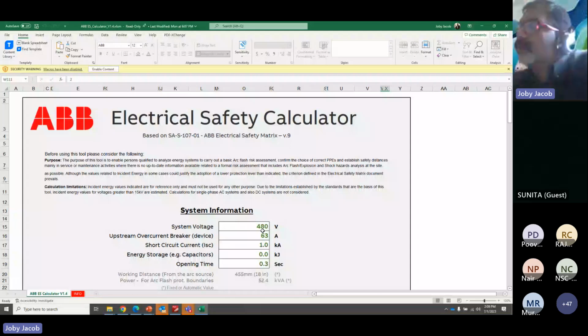And the other important thing is your relay settings, how you set, whether it is instantaneously set or a time delay or something like that. So this is the common mistake also people do. In order to increase the reliability of the machines or the equipment, people take the opening time much higher so that it should not trip. And that's one of the biggest challenges for people who are working nearby.